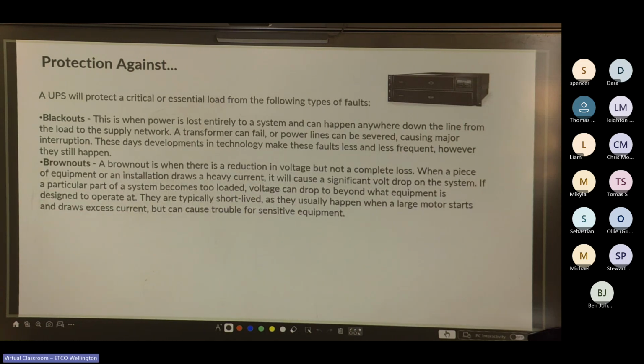Cool. So brownout. A brownout is where there's a reduction in voltage but not a complete loss. So it's when a piece of equipment or installation draws a heavy current, it'll cause significant volt drop on the system. The system becomes too loaded, and voltage can drop beyond what equipment is designed to operate at. Typically short-lived, as they usually happen when a large motor starts and draws excess current, but can cause trouble for sensitive equipment, or it can be caused by a fault in the transformer at the street. I've had a couple of call-outs early on in my career where customers were complaining that their lights were dim and their power points weren't giving enough power. Turns out the transformer at the street had a fault, and Wellington Electricity were going to replace it but hadn't yet.